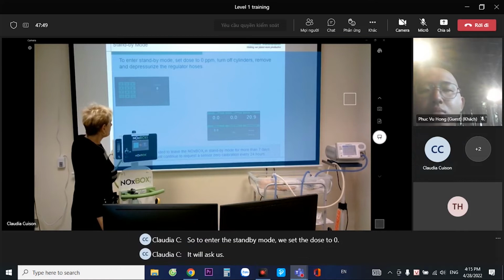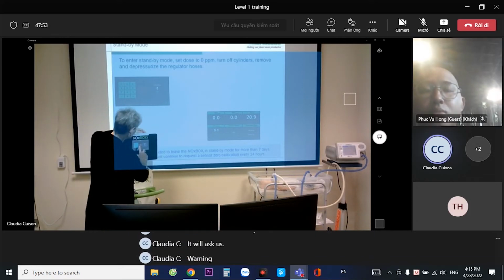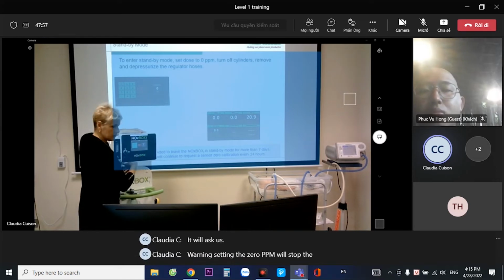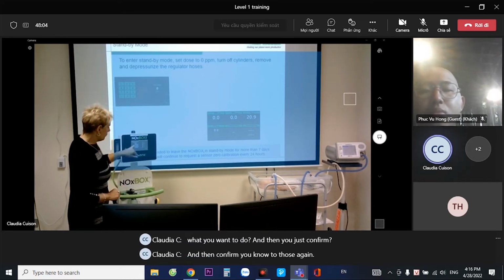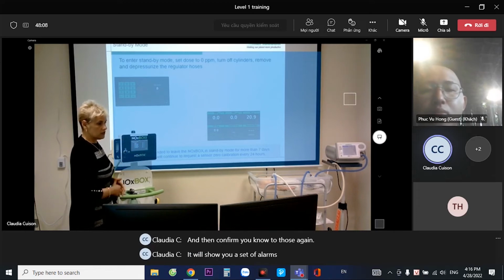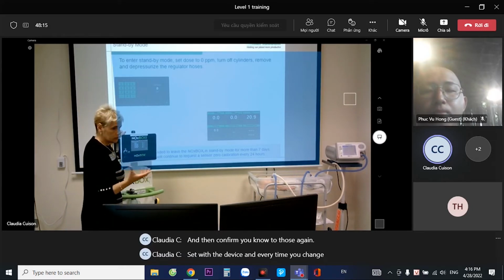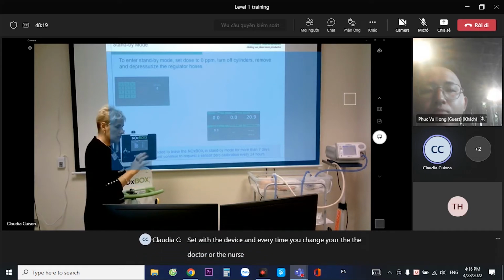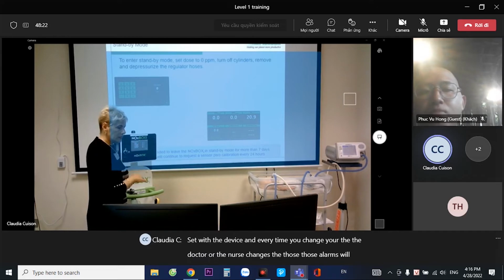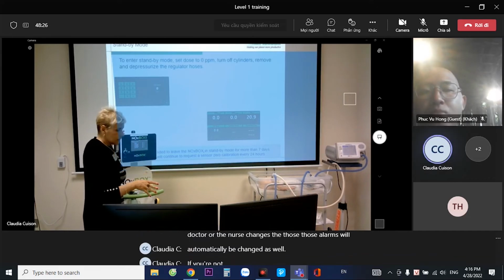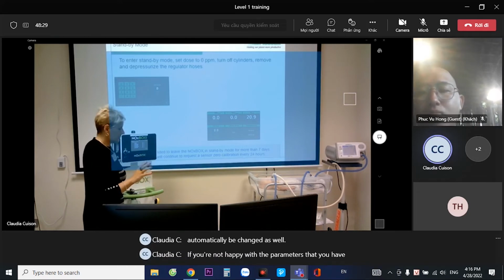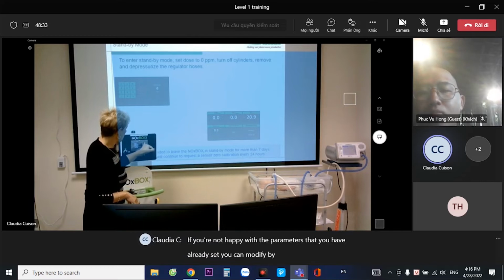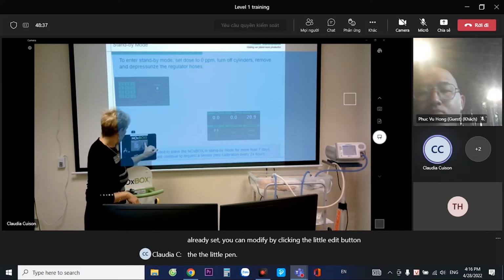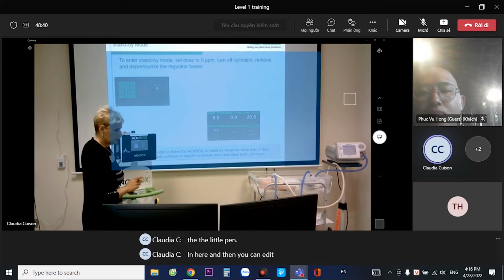It will ask us, warning, setting the 0 ppm will stop the treatment. Is this what you want to do? And then you just confirm. And then confirm NO2 dose again. It will show you a set of alarms, which is automatically set with the device. And every time the doctor or the nurse changes the dose, those alarms will automatically be changed as well. If you're not happy with the parameters that you have already set, you can modify by clicking the little edit button, the little pen in here, and then you can edit according to what you need, right?